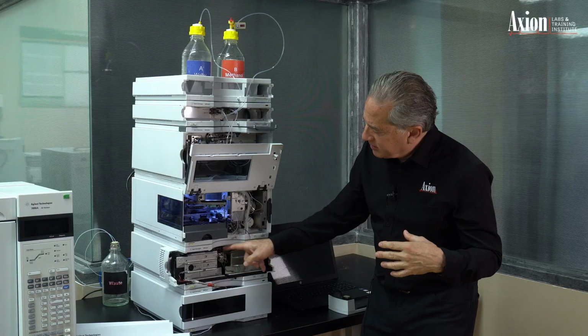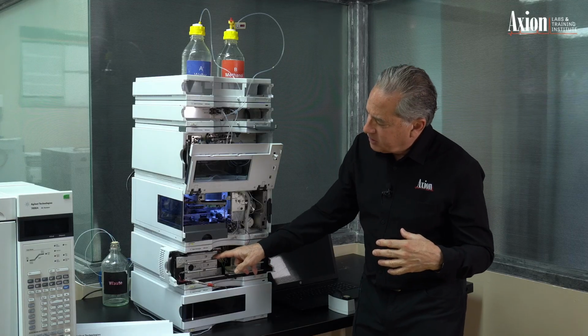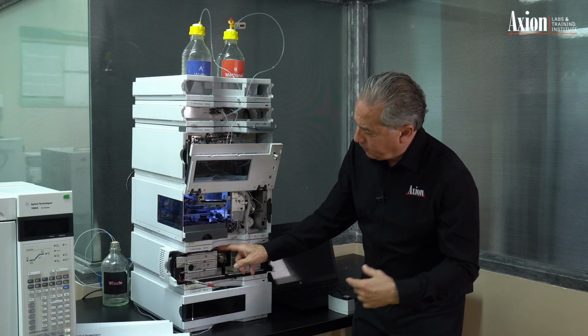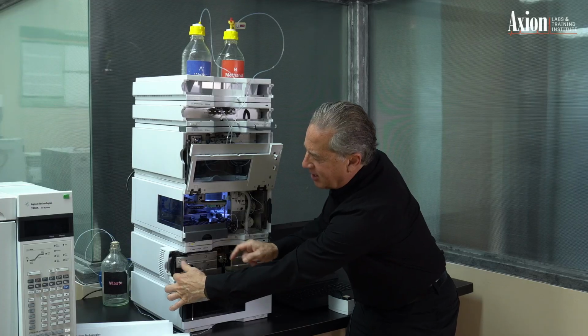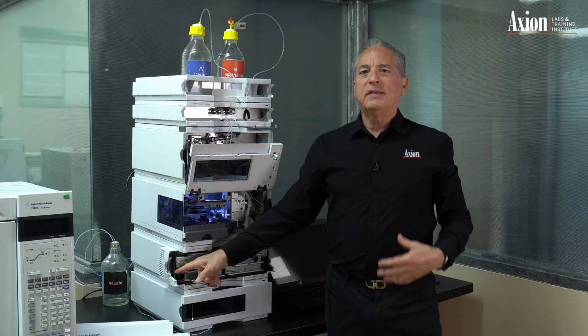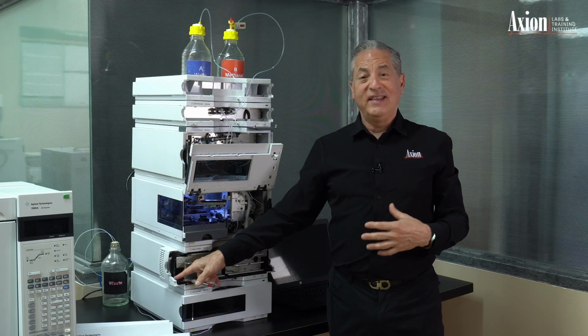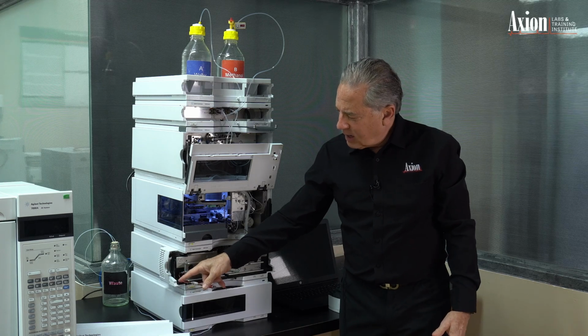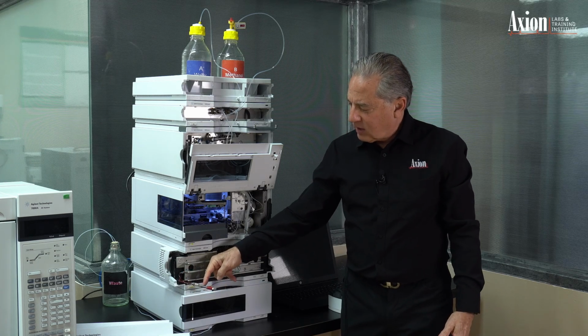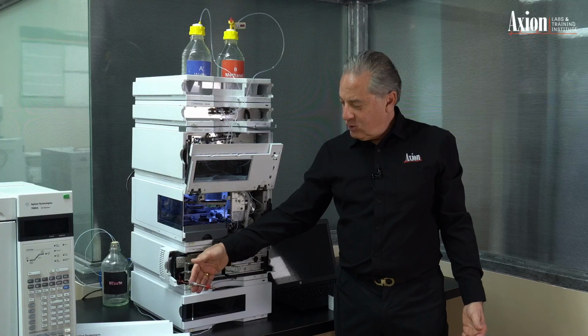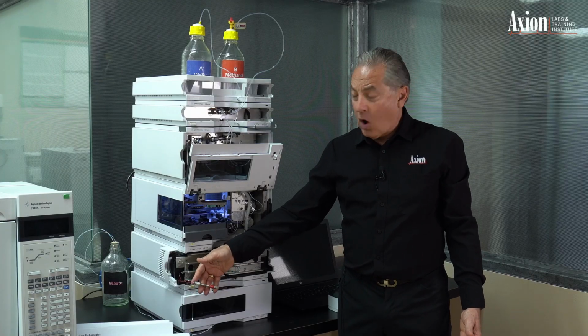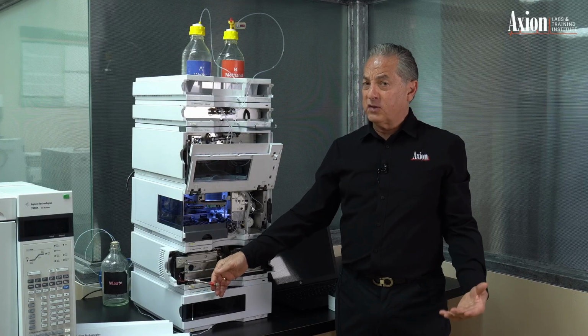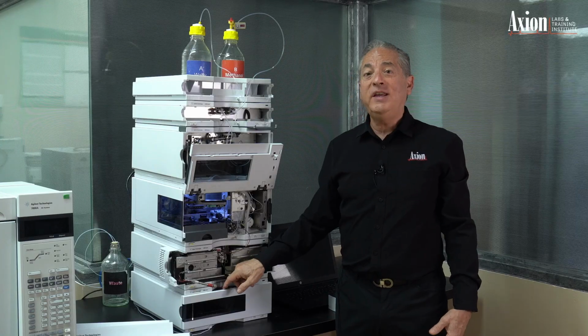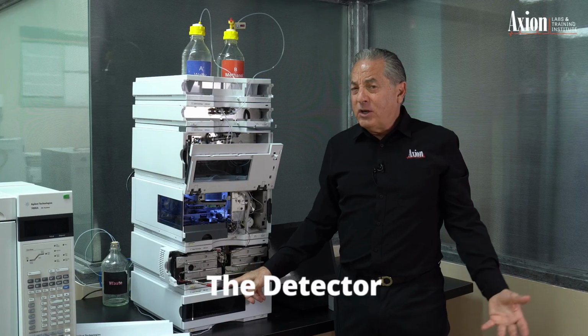So what Agilent does is they go through this heating block first, and it's 3 microliters from here to here. And then coming off here, we now have the sample, the mobile phase, the column all at the exact same temperature. So the sample now comes through here, travels through the column. Here's where the magic happens. This is where we're going to do the separation. And then coming off that column, after we've done our beautiful separation, we now need to detect the molecules. How do we detect it?